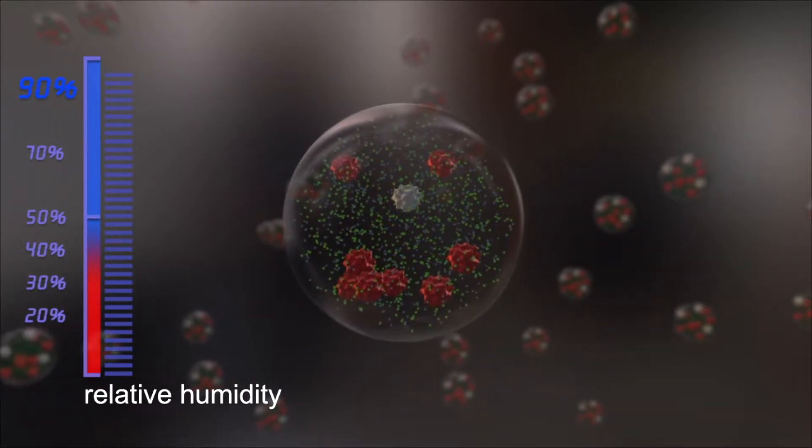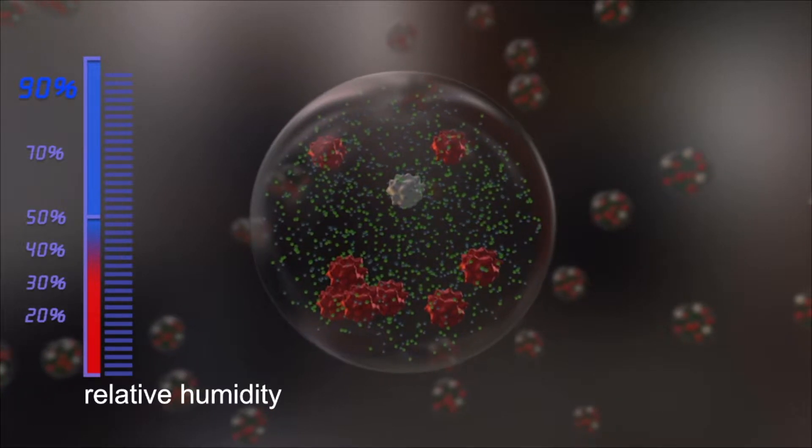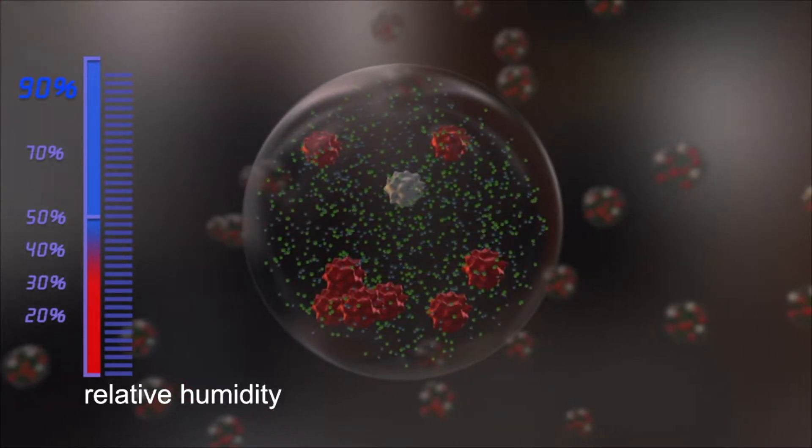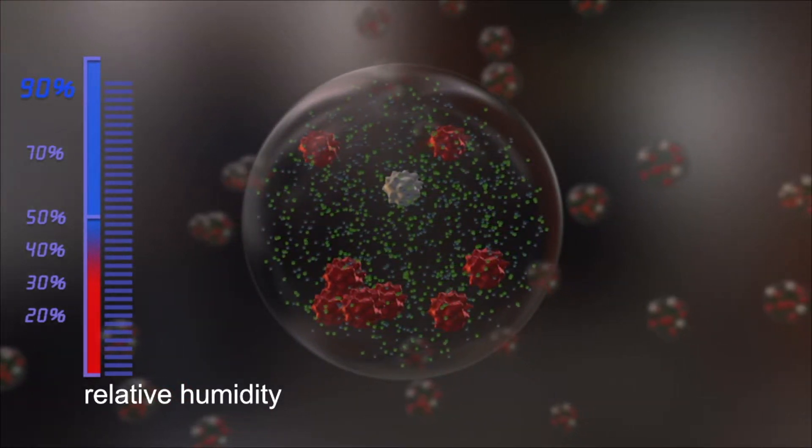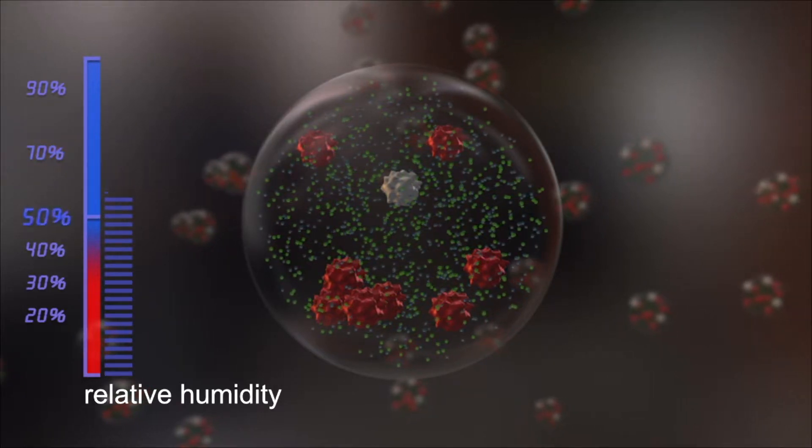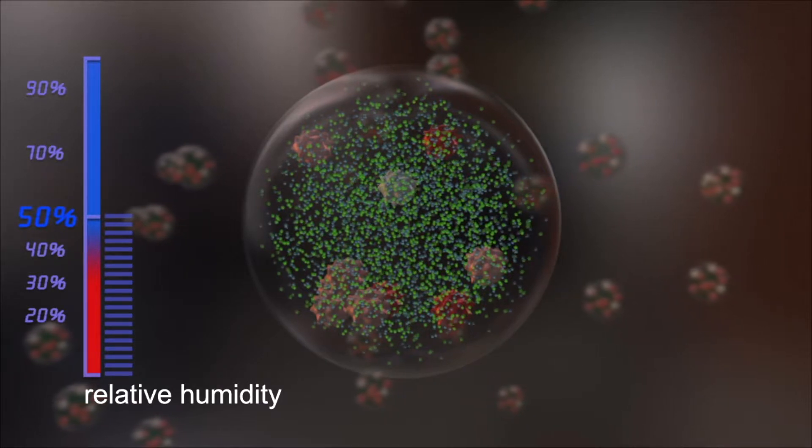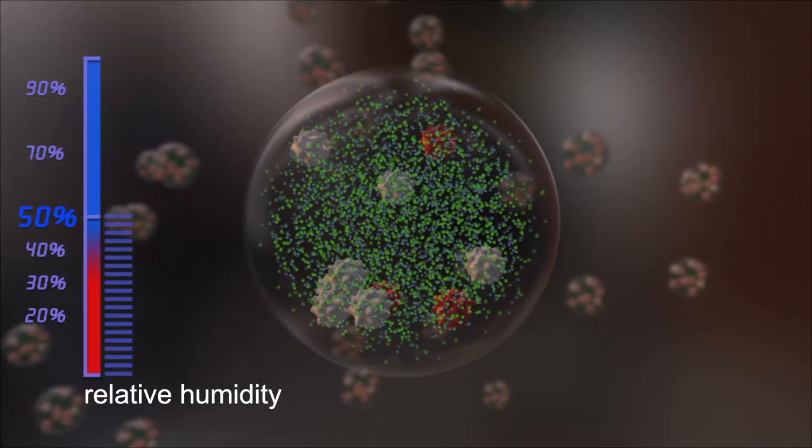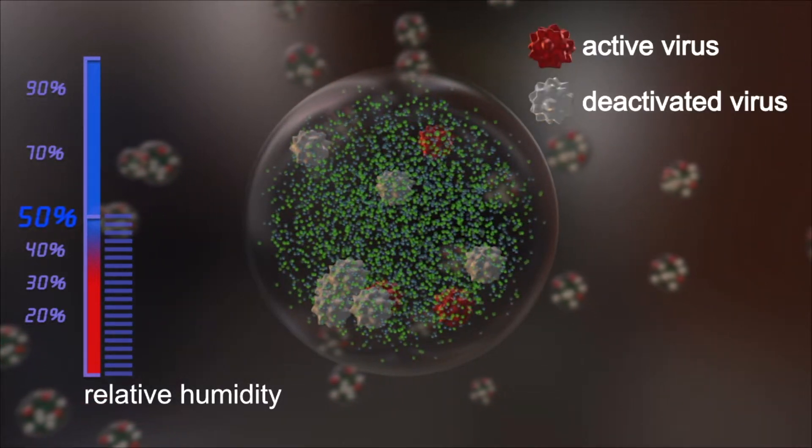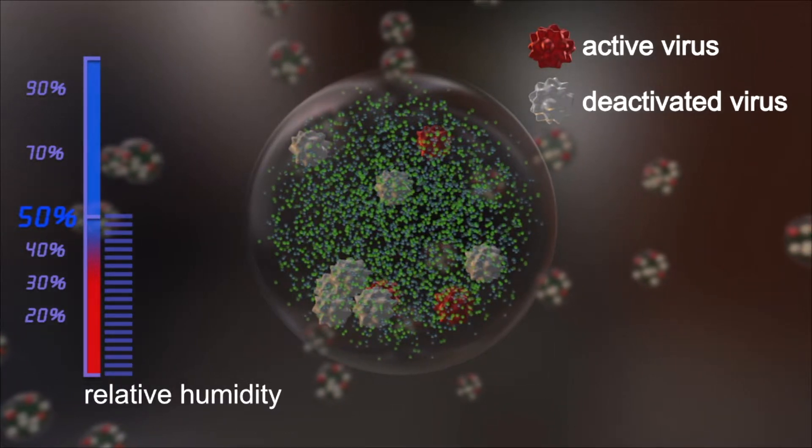If the relative air humidity in the office is within the optimum range for human well-being, namely 40 to 60%, the salt concentration rises to a level where most of the viruses cannot survive and become deactivated. The risk of infection within this optimum range for relative humidity is minimal.